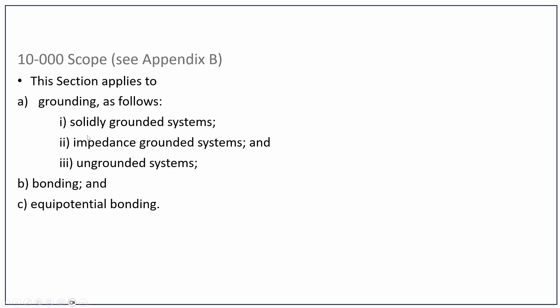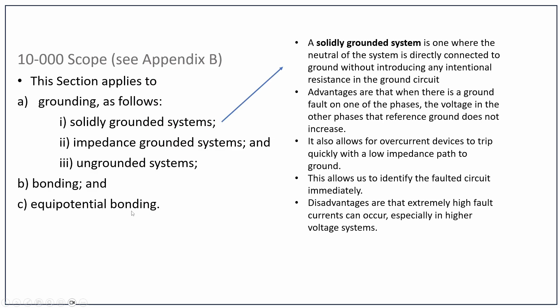Let's first talk about what a solidly grounded system is. A solidly grounded system would be something similar to the panel in your house — it's solidly grounded where the neutral of the system is directly connected to ground without introducing any intentional resistance into the ground circuit. With impedance grounded systems, they actually put a resistor or a coil in order to limit the fault currents. With a solidly grounded system, you have your grounding conductor going to a grounding electrode, or where you have a transformer, the secondary neutral is going to be bonded to ground.